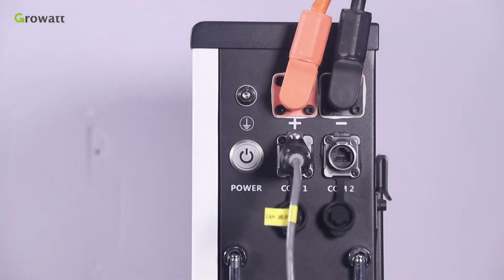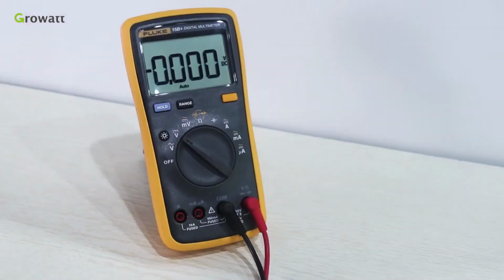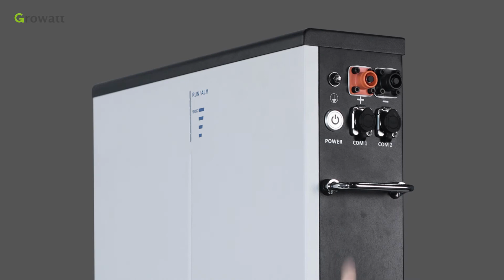Note that you should measure pack voltage with a multimeter and ensure a dual battery system if the voltage difference is measured at more than 1 volt. The difference shall be adjusted to be less than 1 volt either by charging the pack with lower voltage or discharging the pack with higher voltage before conducting the parallel connected installation. Our battery has a one button shutdown function.